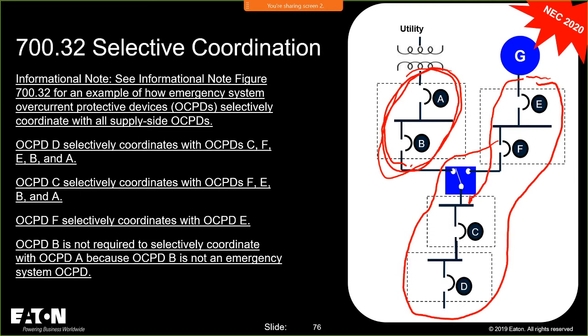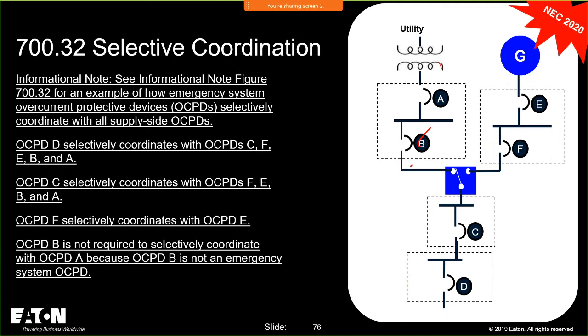And what Code Making Panel 13 keeps getting, and Dan Easter can attest to this, and Mr. Froming, if you're still on this line, you were the instigator of this. You put a public input in saying that these two did have to coordinate with each other, and then you put another public input that said these two do not have to coordinate with each other, and you made Panel 13 address this issue. They did it in an informational note, which was I think a very good addition, because clarity is very important in these things. The lack of clarity gets quotes messed up, it gets the design of the entire system screwed up.